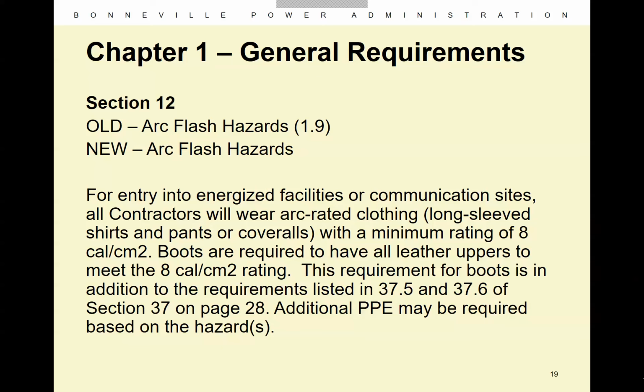Just to add on the arc flash topic, we took a lot of time to make sure our documents aligned with NFPA 70E and OSHA, to make it less confusing for contractors. We didn't want guidance in a BPA document that wasn't in line with OSHA, where a contractor could say BPA said we could do this. So we made sure our documents matched OSHA and NFPA 70E guidance. As for arc flash on the right-of-way, it's really only required for line crews doing hot work, grounding, or ungrounding - anytime dealing with an energized circuit. If the circuit is not energized and is grounded, arc flash isn't an issue, and just walking down the right-of-way it isn't an issue either. Hopefully that answers the question.